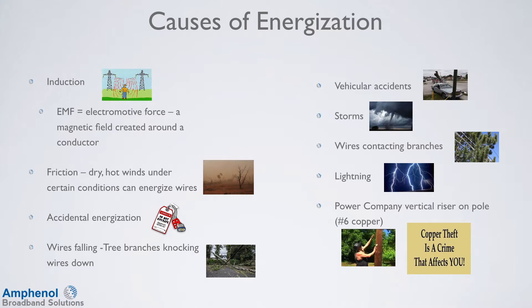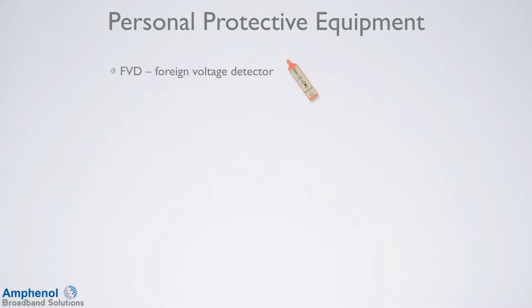Always visually inspect the power company's vertical riser for breaks or missing wire from theft. This wire bleeds inductive voltage from the pole near the primary power lines. If missing near the bottom, the wire above will be energized and waiting for you to become the ground. To protect yourself against electrical hazards, there are several pieces of personal protective equipment. A foreign voltage detector indicates that voltage is present — it does not detect current. The amp clamp measures current flow through a wire and can be used at a tap, ground block, and inside the home. A volt-ohmmeter can be used to measure voltage, current, and resistance.